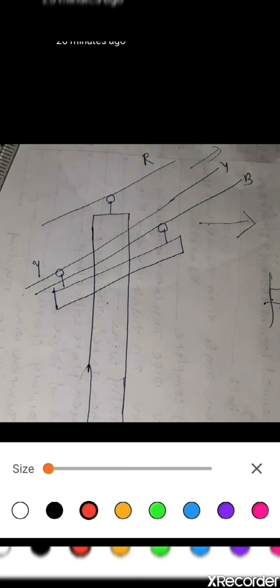Previously the existing pole looks like this. Here only the pole is there and one cross arm, and the three phase lines, that is R phase, Y phase and B phase, are going along this direction, and the three phase lines are suspended on pin type insulators. But we have to take the connection along this direction because our proposed site is along this direction. So we have to make some new arrangement on this pole so we can take the connection along this direction.